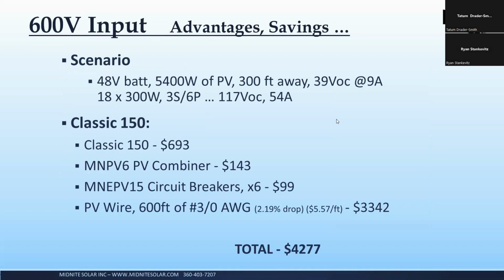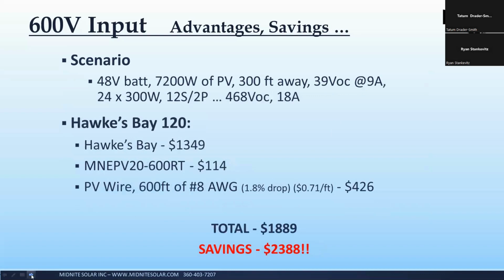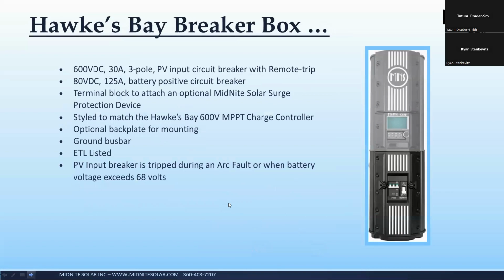This is just a pricing example of why high voltage is better than low voltage when it comes to the cost of the wire, the cost of the breakers, the cost of the combiners, and all of that. It's kind of a no-brainer if you can run a single pair of 10 gauge wires back versus number 4 and combiner boxes and everything else. It's going to be less expensive.